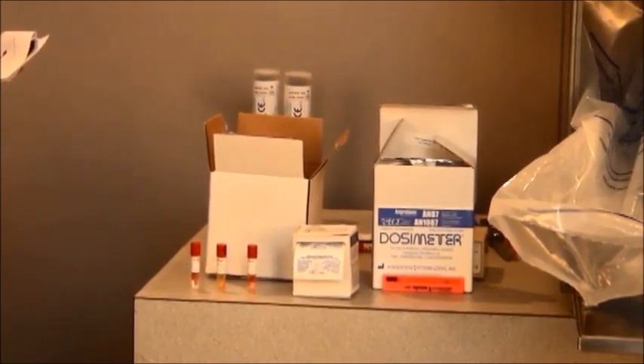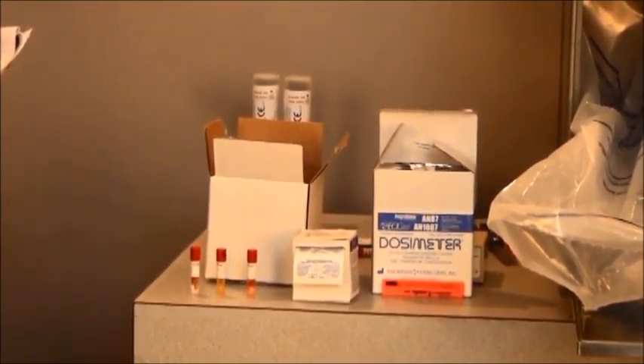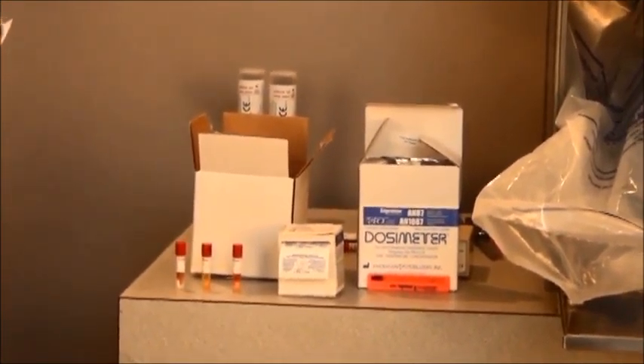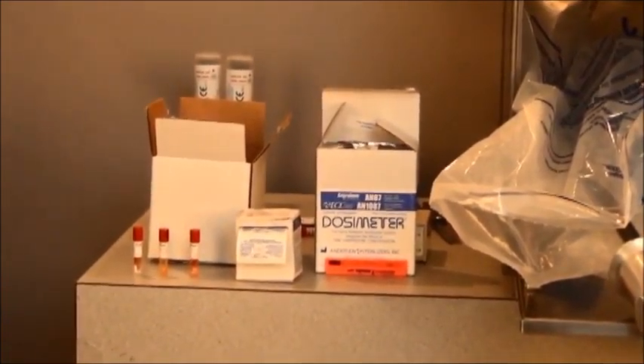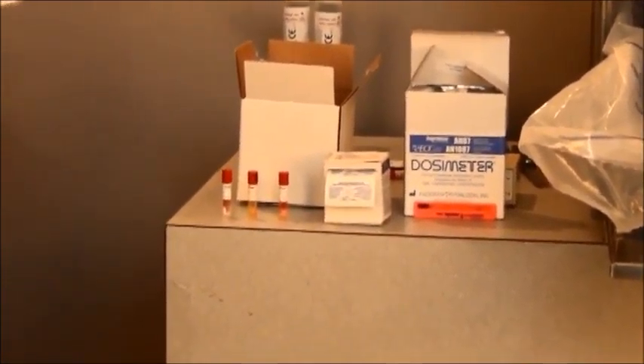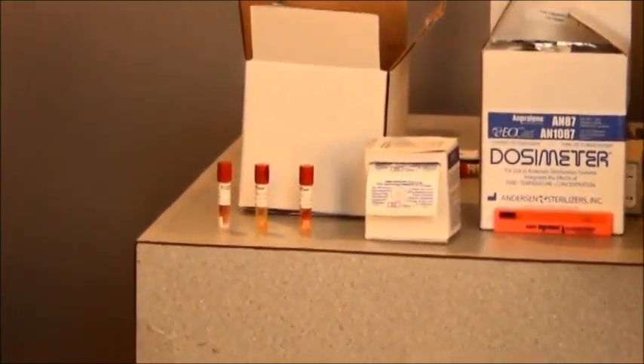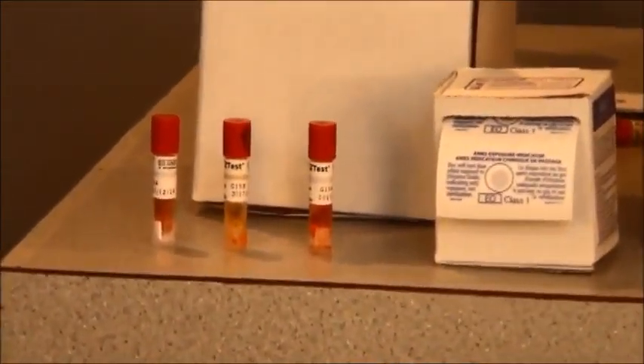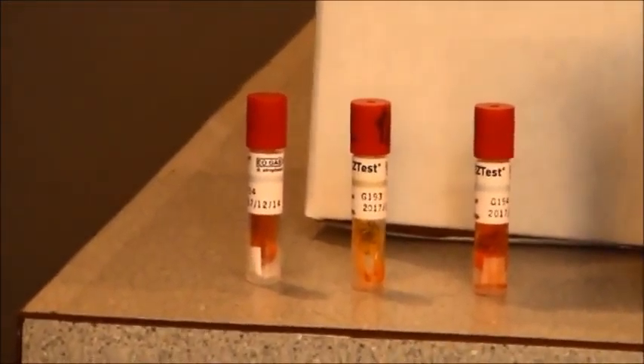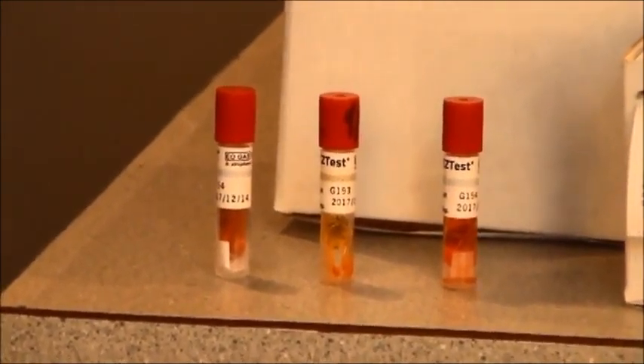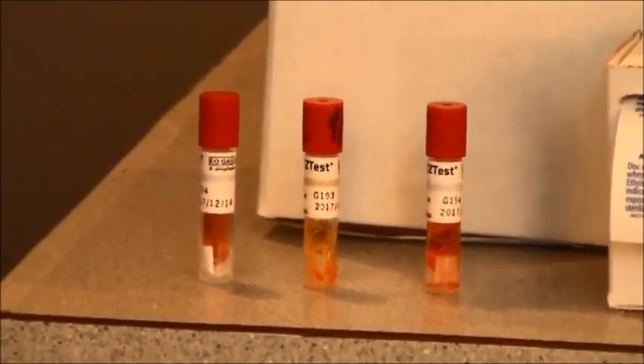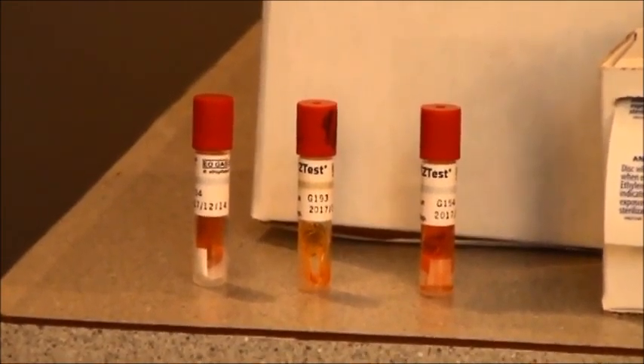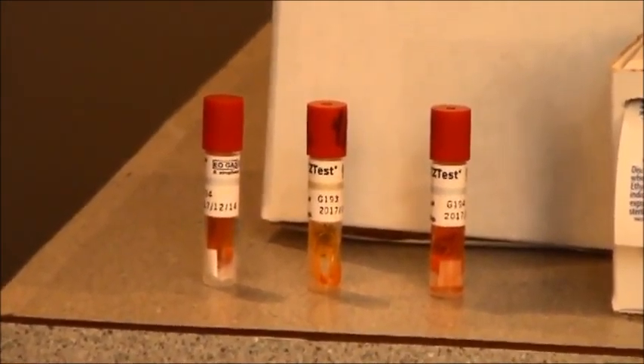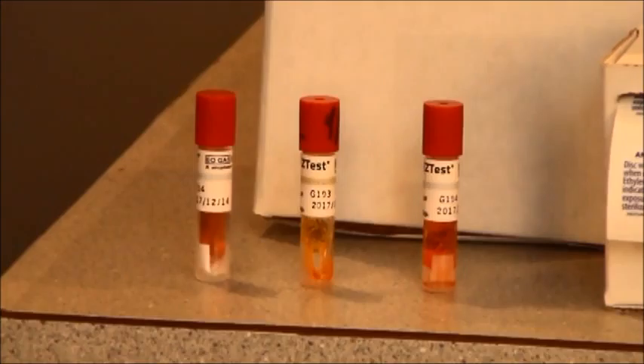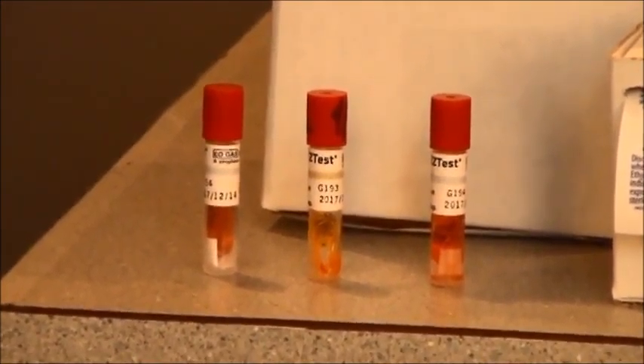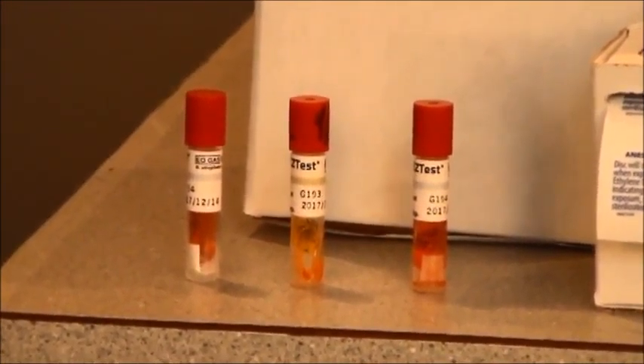One important note about your different types of indicators. We have three indicators shown here that are utilized in your sterilization cycle. You have your biological indicator on the far left. This is placed inside of your process control device. Your biological indicator uses live spores to confirm the success or failure of your sterilization cycle. Always follow your manufacturer's recommendations when using biological indicators.